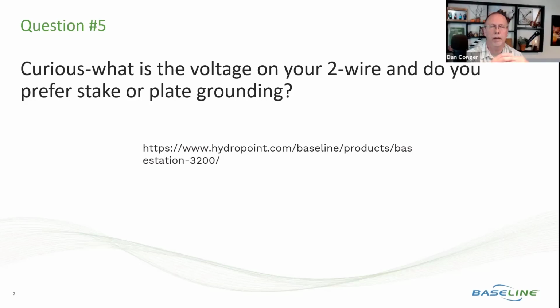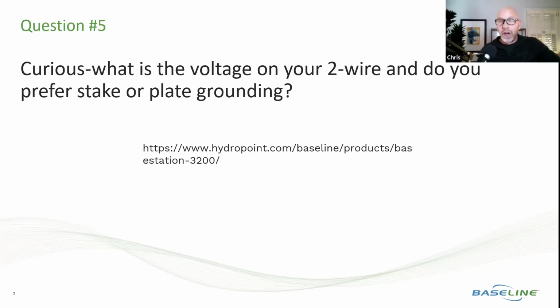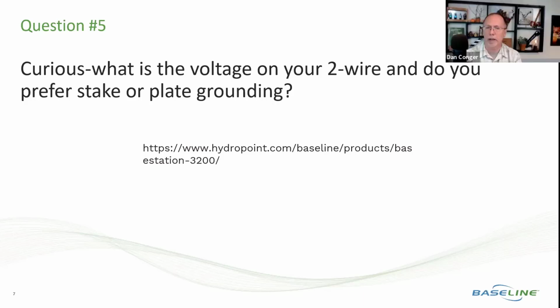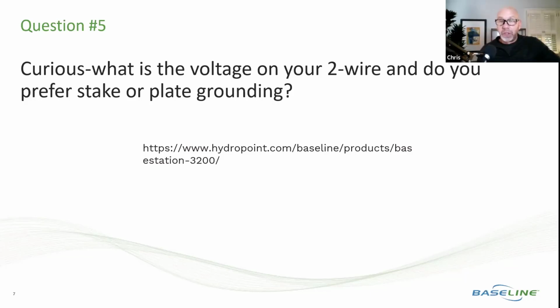Yeah. The other thing that's part of our spec is the distance of that ground point from the wire path. That was the other thing that we're concerned about as well. Yep. So if it's an 8-foot ground rod, then it needs to be 8 feet away, perpendicular from the wire path. Correct. Yep. No closer than 8 foot. And then plates are basically take that diagonal distance, and that's the distance it needs to be from the wire path. Yep. And typically that would be below if you're using a plate, because they often get installed in narrow planter beds or park strips or on green roofs or other applications.